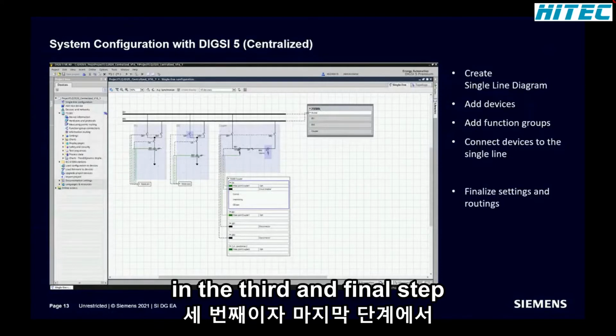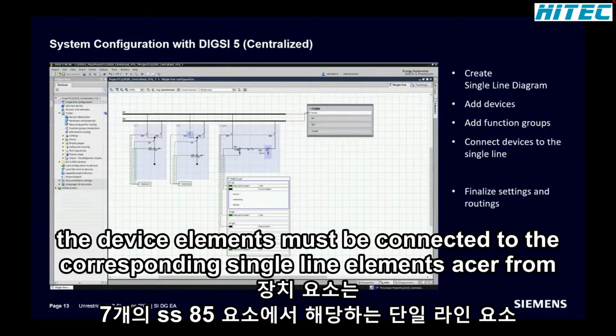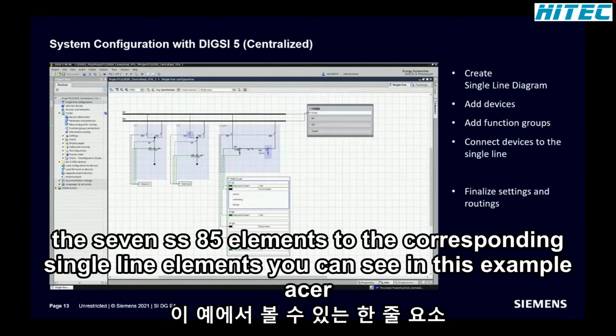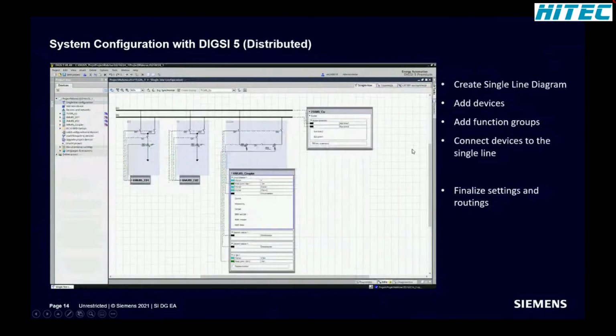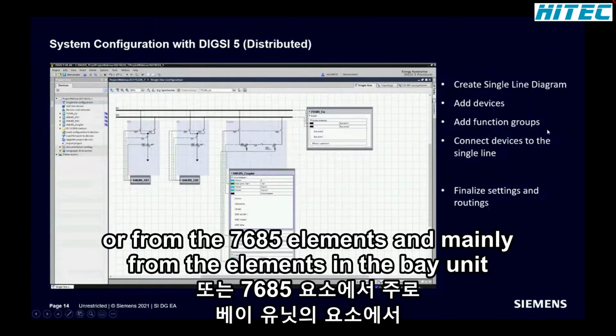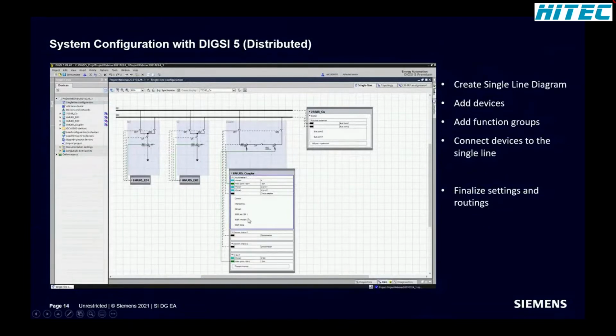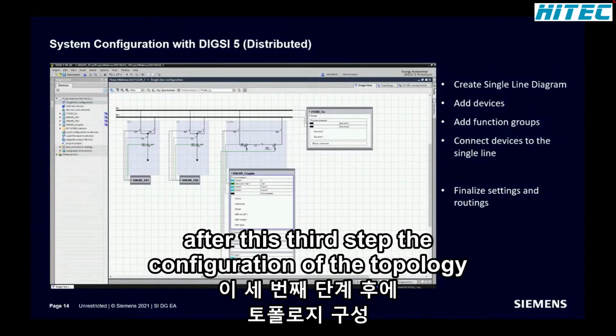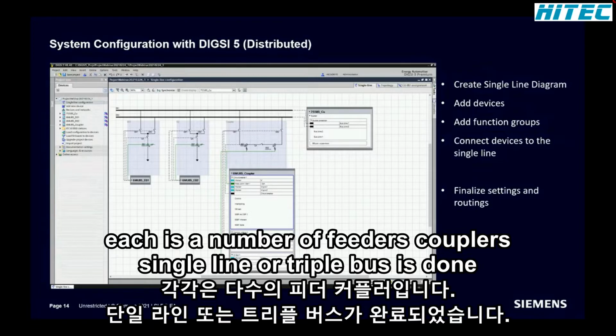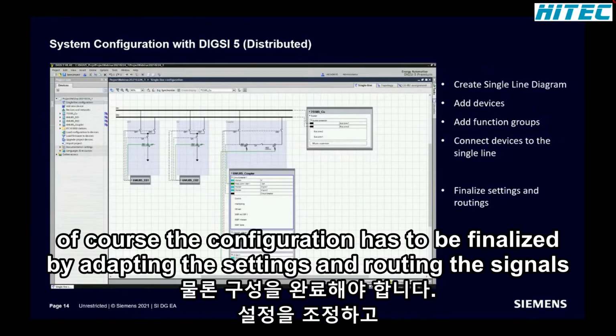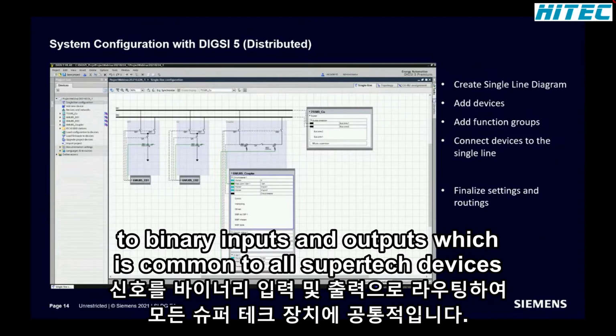In the third and final step, the device elements must be connected to the corresponding single line elements, either from the 7SS85 elements to the corresponding single line elements, as you can see in this example, or from the 7SS85 elements, and mainly from the elements in the bay unit, to the corresponding single line elements. After this third step, the configuration of the topology, e.g. the number of feeders, couplers, single line or triple bus, is done. Of course, the configuration has to be finalized by adapting the settings and routing the signals to binary inputs and outputs, which is common to all SIPROTEC devices.